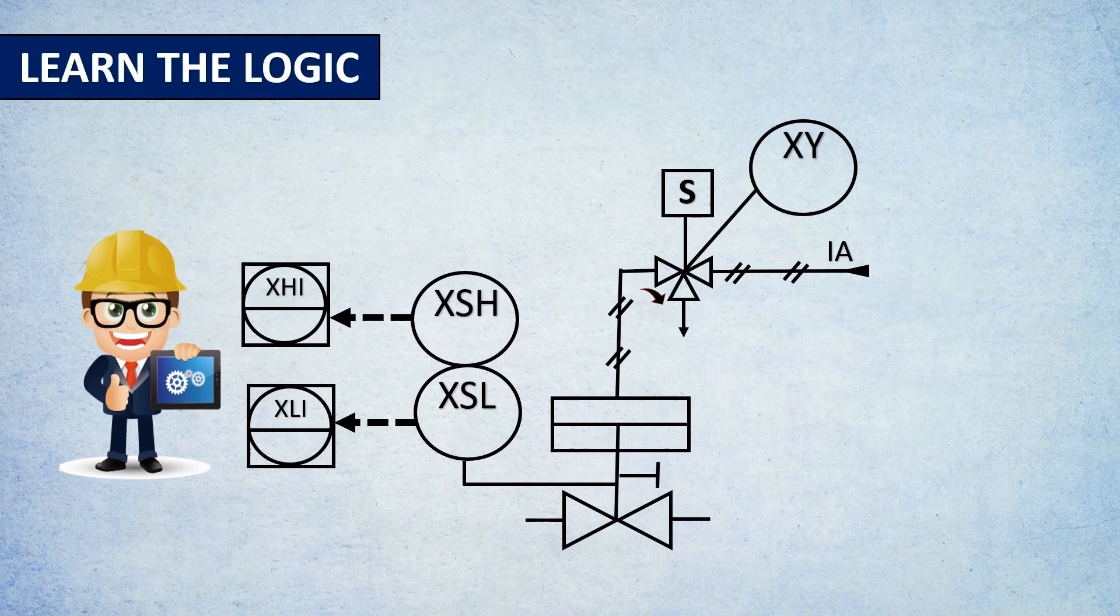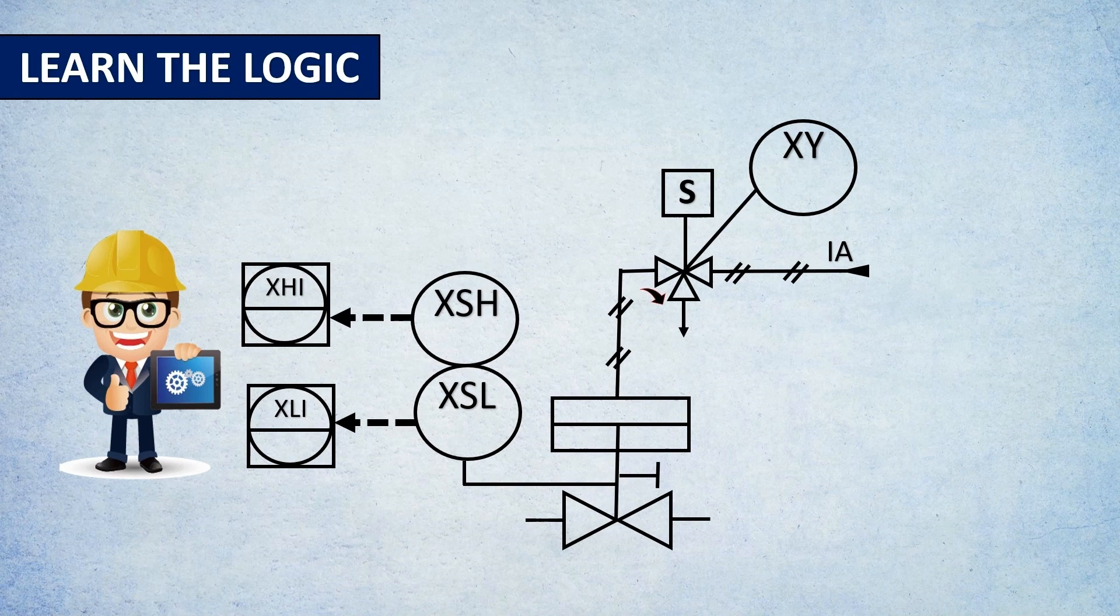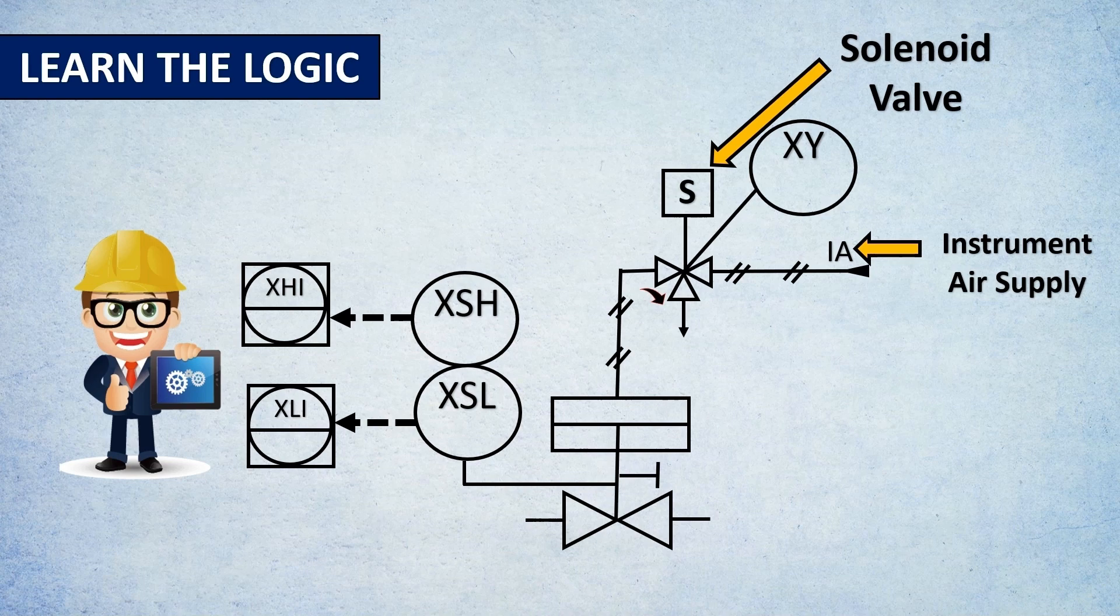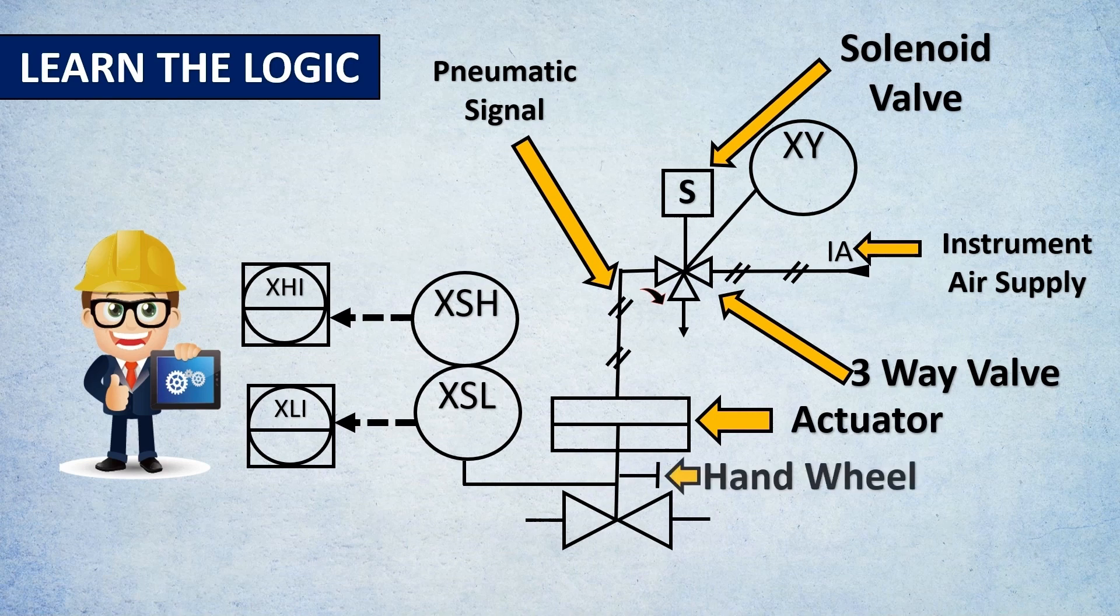Let's understand the proper logic of how this valve works, especially the de-energizing path. Here's our instrument air supply, then the solenoid valve. What type of solenoid valve is this? This is a three-way solenoid valve. Then you have a pneumatic signal that goes to your actuator, a hand wheel, and the body.